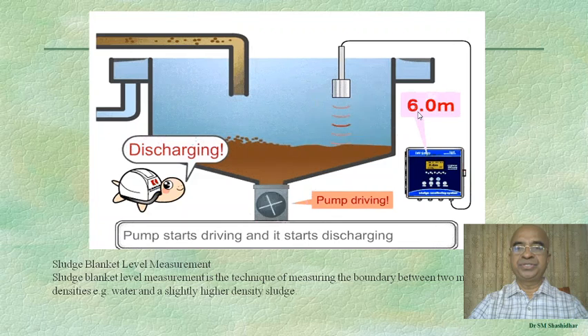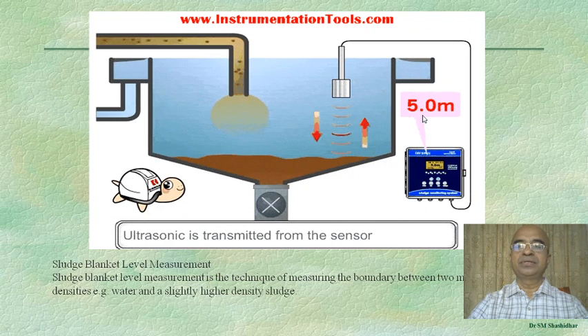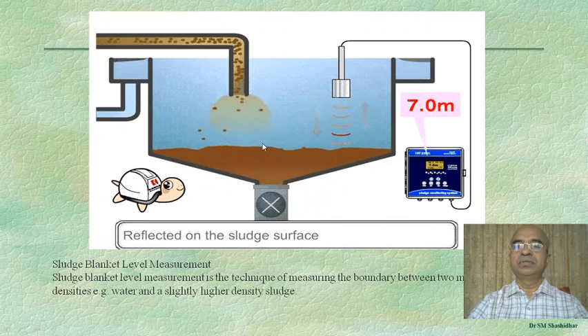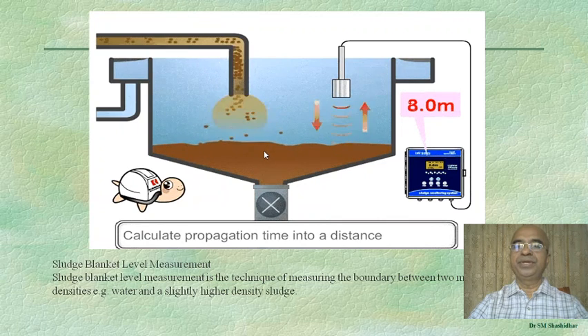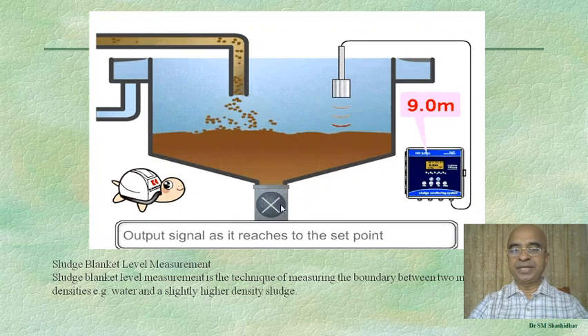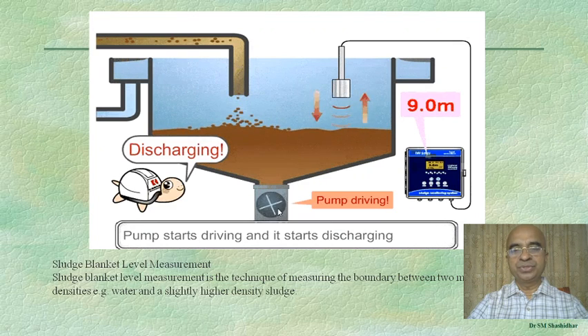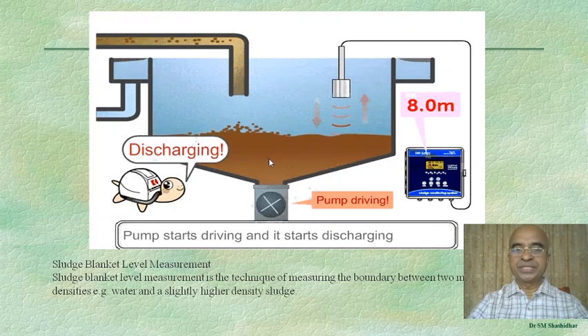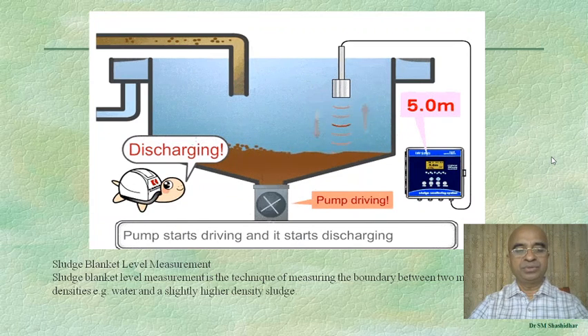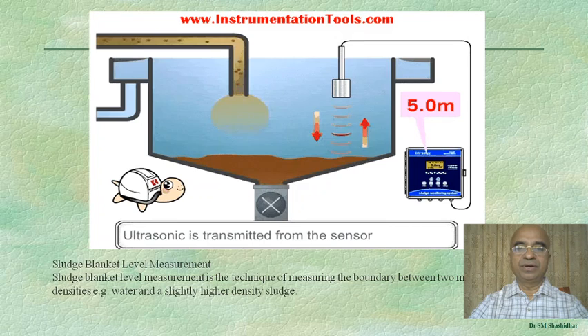The sludge level is continuously changing. When it drops to 5 meters, the valve is closed and sludge flows from the pipe into the tank again. When it reaches 8 to 9 meters, the valve opens and the sludge is discharged. This is one example of how liquid or sludge level monitoring is done in practice.